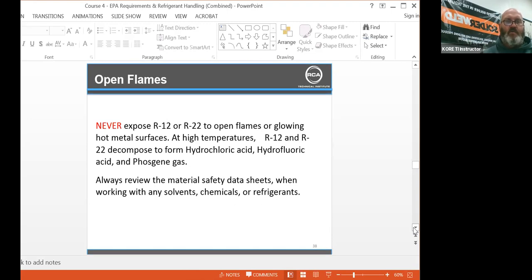Never expose R12 or R22 to open flames. On a glowing or hot metal surface at high temperatures, R12 and R22 decompose and form hydrochloric acid, hydrofluoric acid, and phosgene gas. You guys know once you get that smell of phosgene, you never get it out. Always review the material safety data sheets, MSDS, when working with solvents, chemicals, or refrigerants.